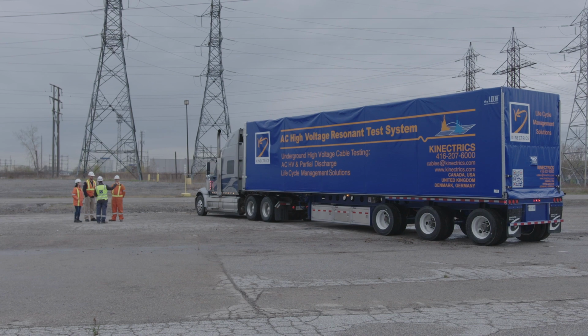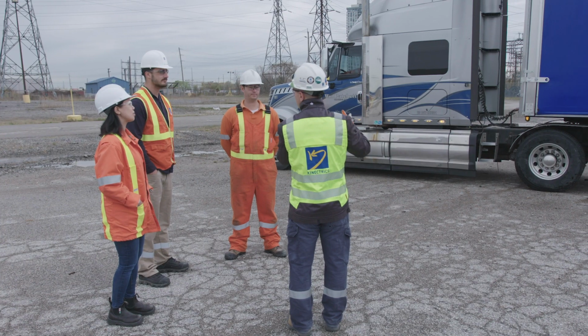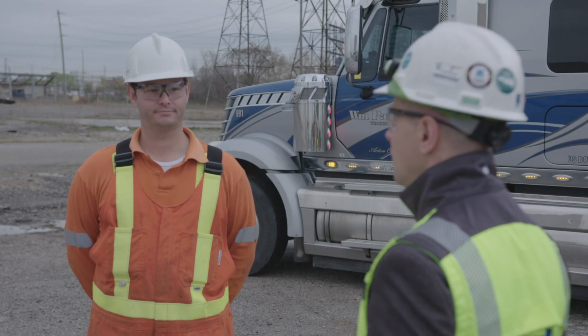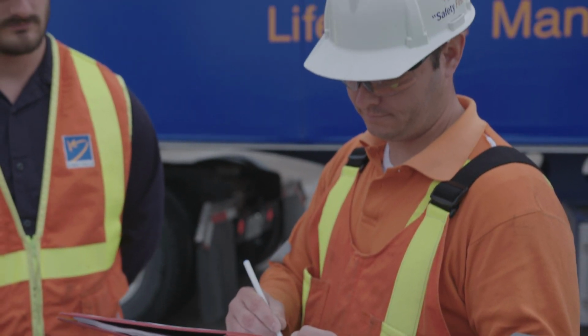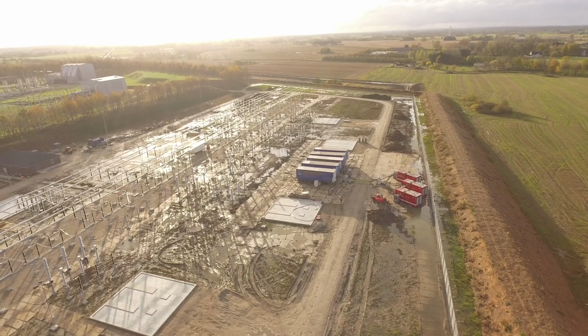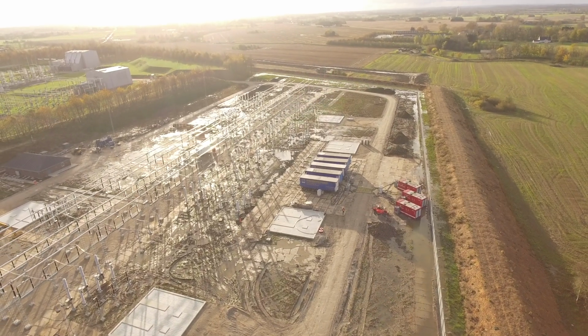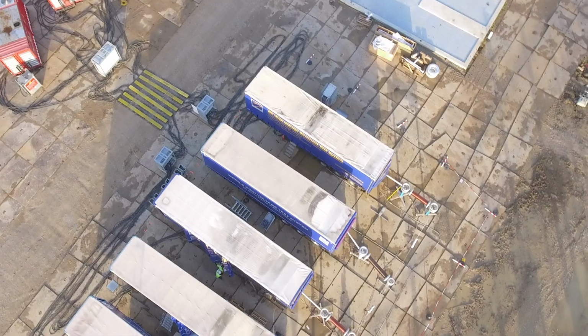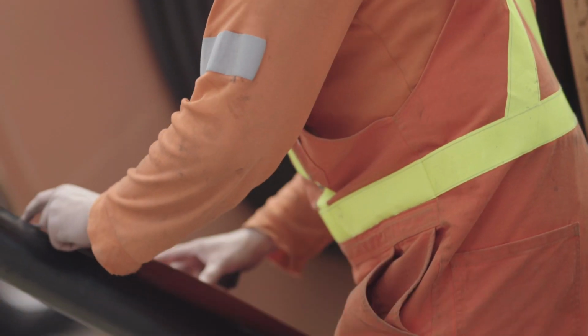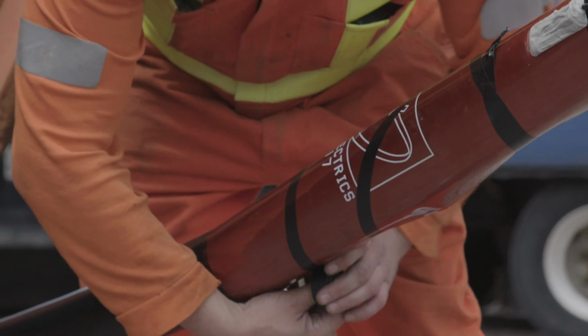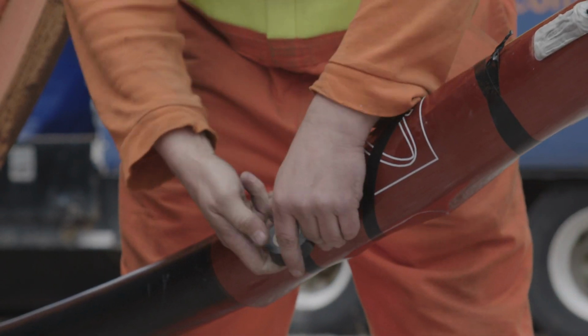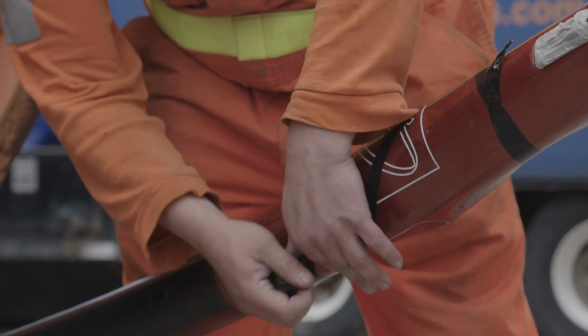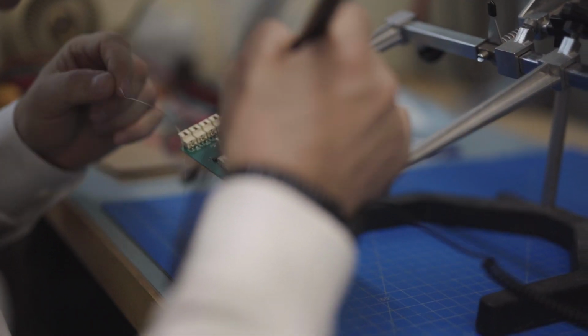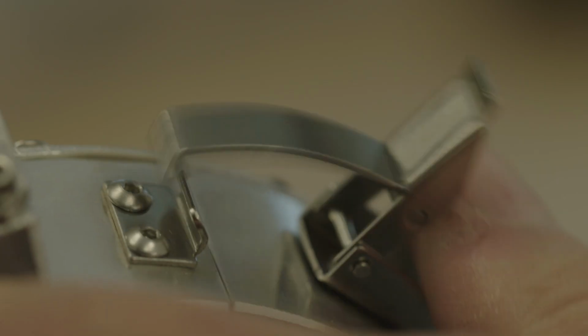So we have a fleet of RTS systems strategically located in Europe and in North America, and we can move them around between those regions, depends on the cable's length. We have multiple units. We can provide our own equipment to energize long and high voltage cable lines, either in parallel configuration, series configuration, or mixed configuration. We're independent of not only users, cable manufacturers and installers, but also test equipment providers. So this enables us to avoid any pressure and enables us to use whatever techniques and equipment are most appropriate.